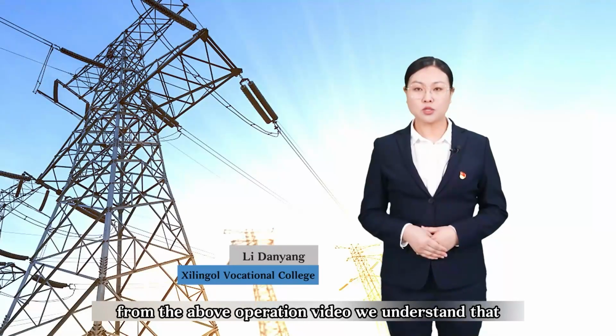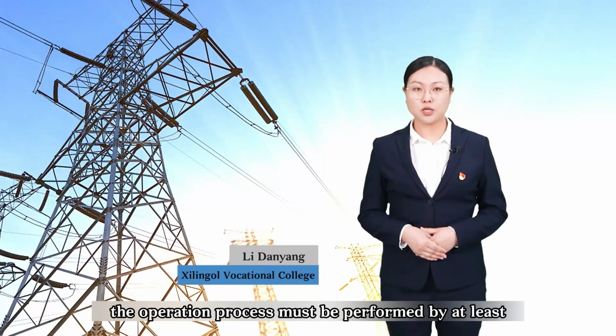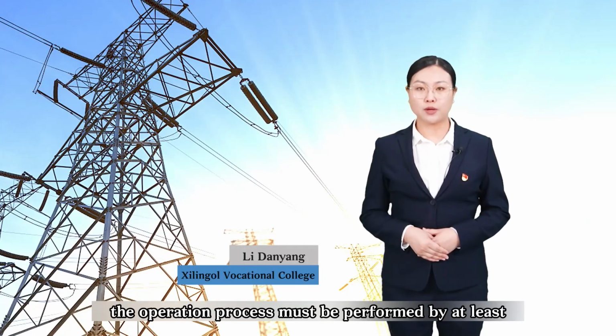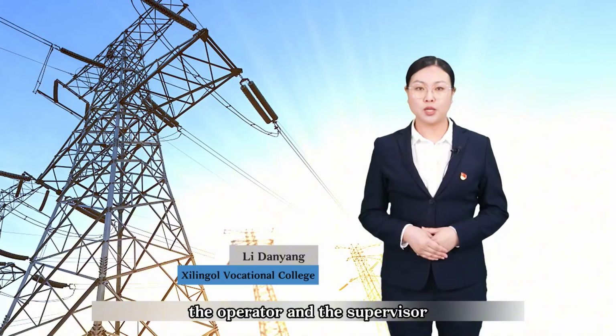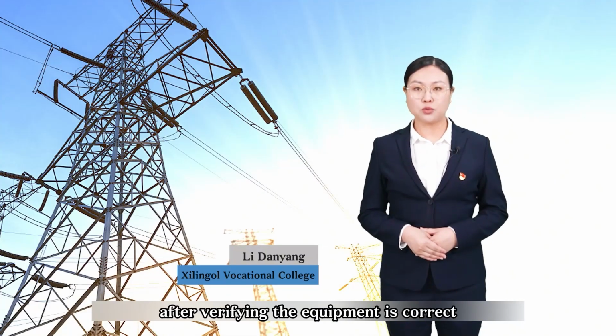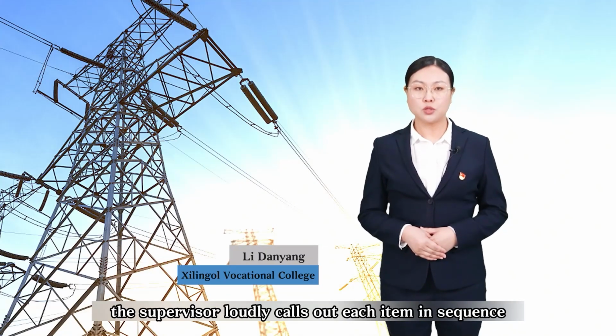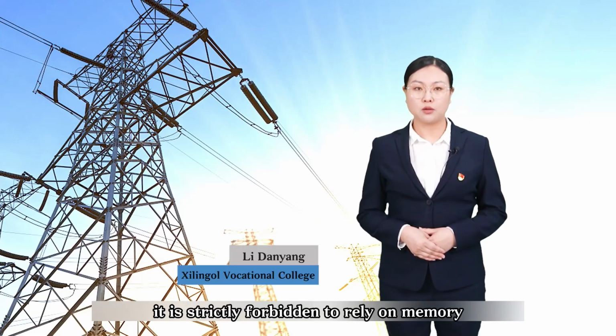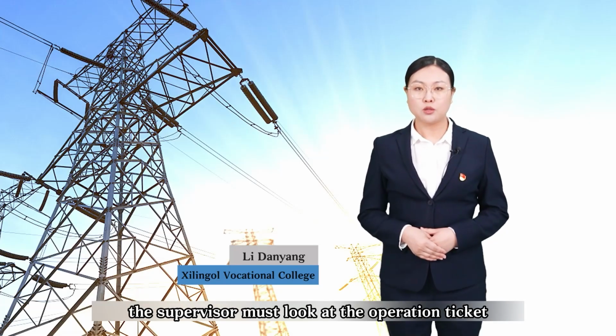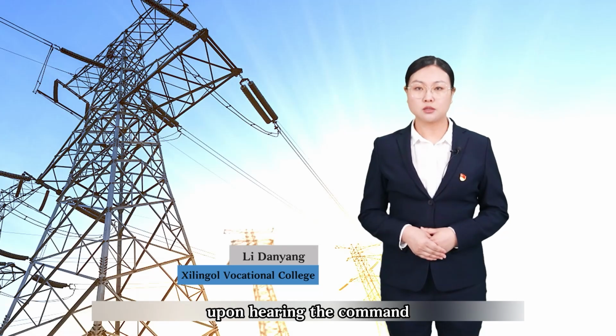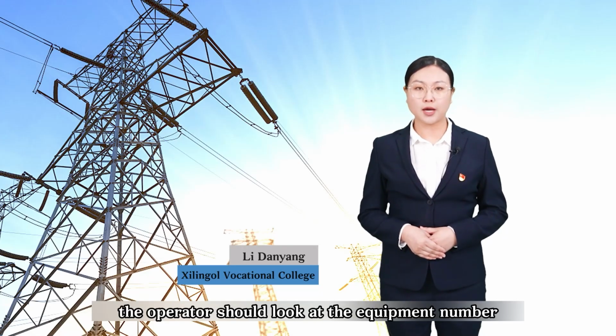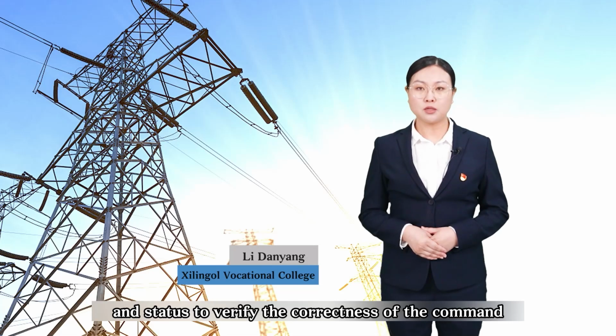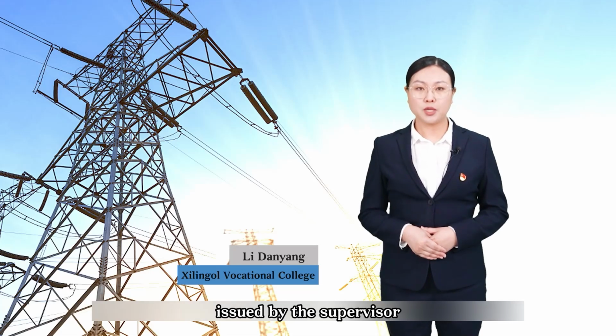From the above operation video, we understand that the operation process must be performed by at least 2 staff members, the operator and the supervisor. After verifying the equipment is correct, the supervisor loudly calls out each item in sequence. When calling out, it is strictly forbidden to rely on memory. The supervisor must look at the operation ticket and call out each item loudly. Upon hearing the command, the operator should look at the equipment number and status to verify the correctness of the command issued by the supervisor.